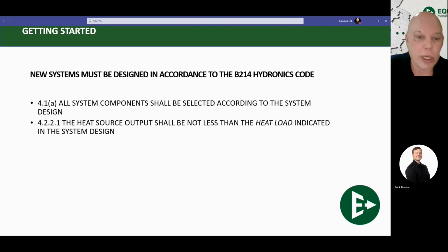4.2.2.1: The heat source, meaning the boiler, or in some cases an air-to-water heat pump or whatever, the heat source output shall not be less than the heat load indicated in the system design. A couple of things to unpack here. Number one, a bit of common sense. If you do a heat loss for the building or the home and the heat loss is 50,000 BTUs and you put in a 30,000 BTU boiler, that's not going to be large enough. You have to meet or exceed the heat load indicated in the system design. The second part of that is where it notes system design. The system has to be owned by someone. Someone needs to take legal responsibility for this system: contractor, BCIN holder, or a P.Eng. That's your three options.